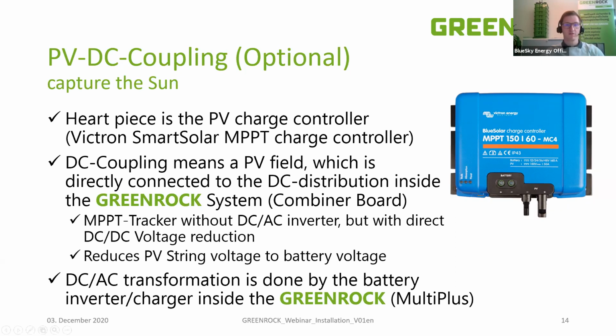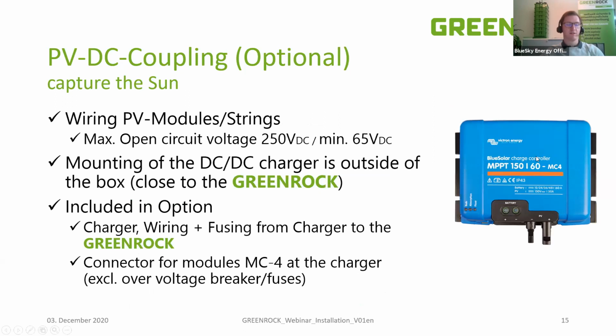Also really important is that right now these DC-DC chargers are only available with an input voltage of 250 volts. So if you're used to inverters like SMA, where string voltages go up to 1000 volts, it's a bit different here. The maximum DC voltage is 250 volts, so you cannot connect all the solar panels in series; you also have to make a few parallel strings with this option.